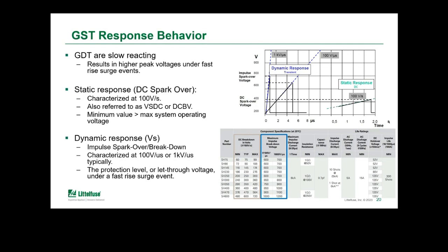The other characteristic is the dynamic response, which is also referred to as impulse spark over or breakdown voltage. This is characterized using 100 volt per microsecond or 1,000 volt per microsecond, typically. And this represents more of the protection level, or the let-through voltage that could be seen by the circuit. This occurs under an ultra-fast surge event, or with a fast rise time. You can see the difference here: as the response time decreases, the let-through voltage increases, depending upon the rate of rise of the transient event. So GDTs in general are slow reacting and result in higher peak voltages under fast rise surge events.